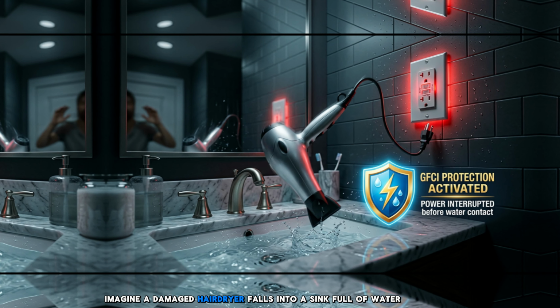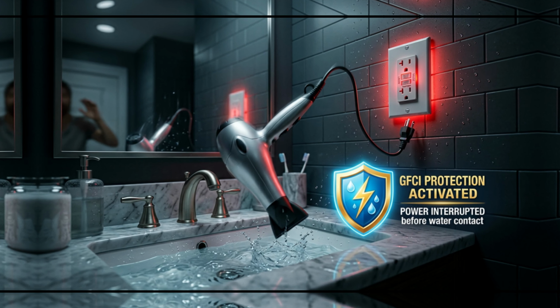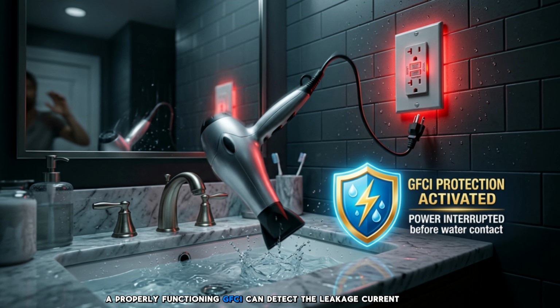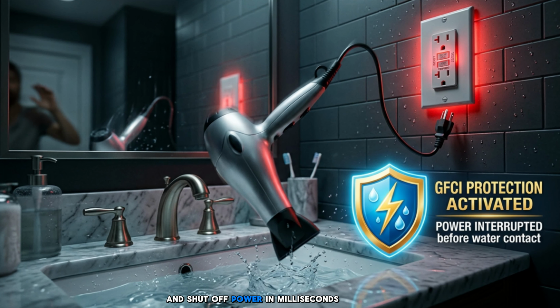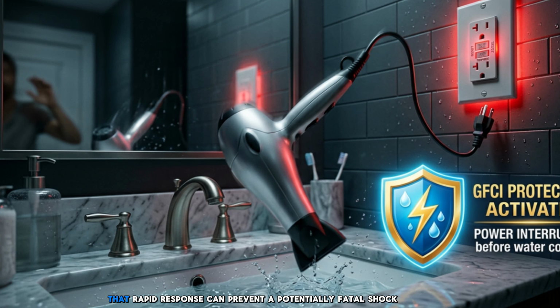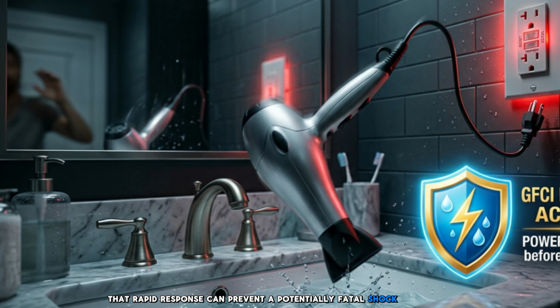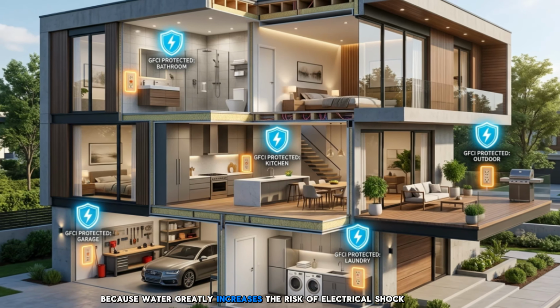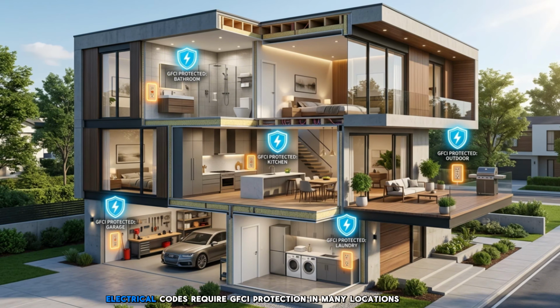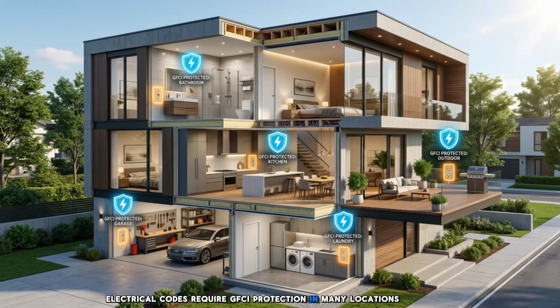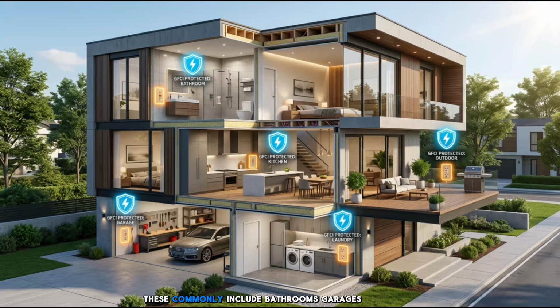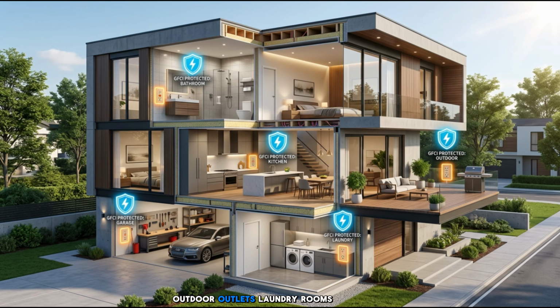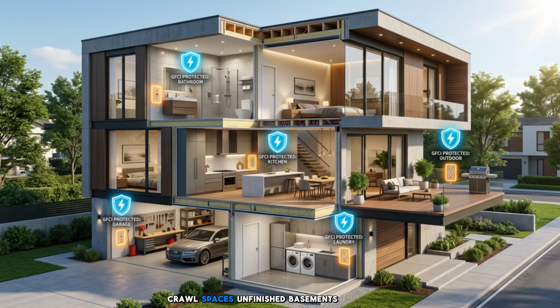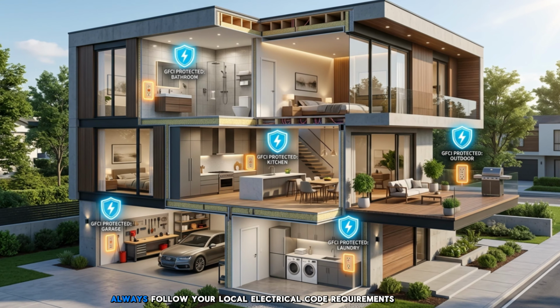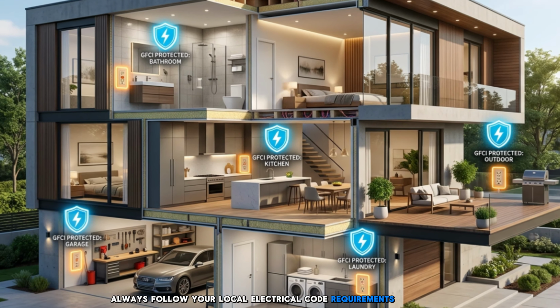Imagine a damaged hairdryer falls into a sink full of water. A properly functioning GFCI can detect the leakage current and shut off power in milliseconds. That rapid response can prevent a potentially fatal shock. Because water greatly increases the risk of electrical shock, electrical codes require GFCI protection in many locations. These commonly include bathrooms, garages, outdoor outlets, laundry rooms, crawl spaces, unfinished basements. Always follow your local electrical code requirements.